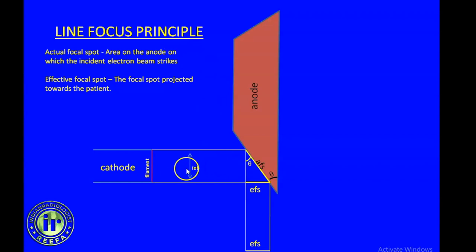The first term is the Incident Electron Beam. It is the electron beam that emanates from the filament from the cathode side and bombards the target anode. The area on the anode where this incident electron beam strikes is called the actual focal spot. The focal spot projected towards the patient side is called the effective focal spot, also called the apparent focal spot, because it appears to be of a different width than the actual focal spot, which is achieved by the angulation of the anode.